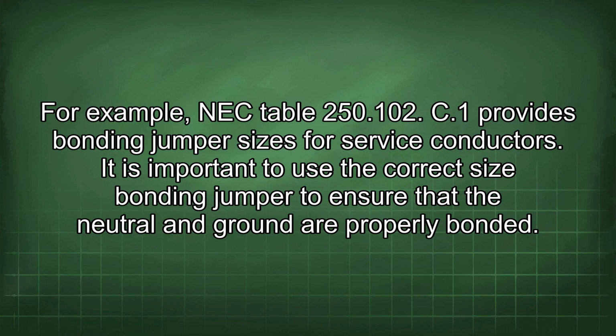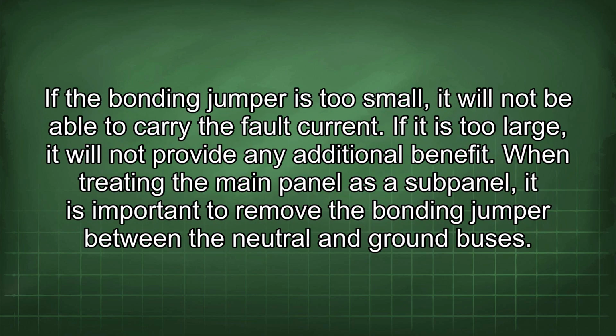250.102(C)(1) provides bonding jumper sizes for service conductors. It is important to use the correct size bonding jumper to ensure that the neutral and ground are properly bonded. If the bonding jumper is too small, it will not be able to carry the fault current. If it is too large, it will not provide any additional benefit.